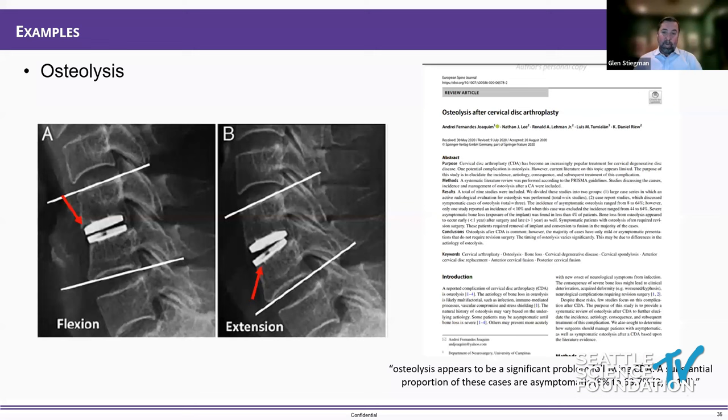From my standpoint, it really is, how is this advancing? Is it stabilizing? The FDA is incredibly sensitive to this right now, especially with M6-C, and it will be built into protocols moving forward. It'll be interesting to see how we trend towards calling these failures before there's any pain signal or anything else. So I think FDA is continuing to move towards making some of these observations more clinically related, expected clinical scenarios that they'll deem failures.